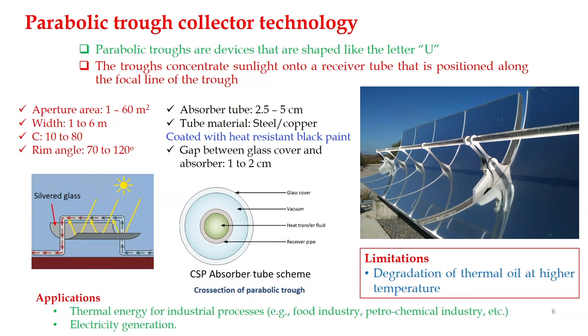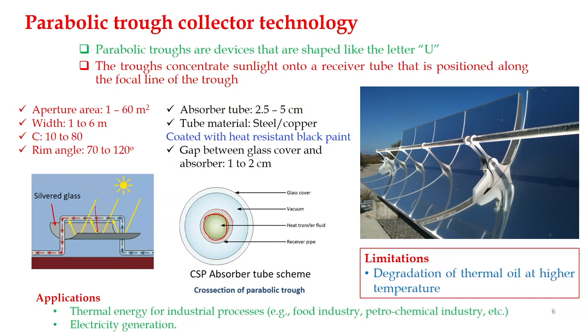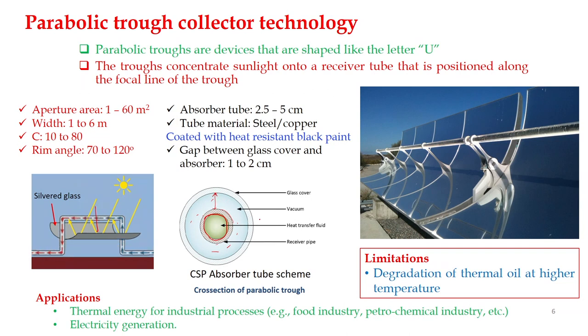The absorber cross-section: heat transfer fluid flows through the inner tube, which is normally steel or copper. There is a vacuum between the tube and the glass cover, which reduces convective heat transfer — meaning heat loss is reduced by providing this vacuum. This gap between the two is normally 1 to 2 centimeters.